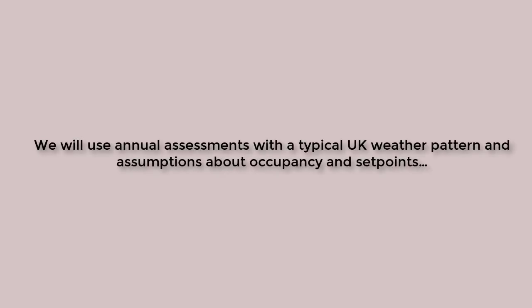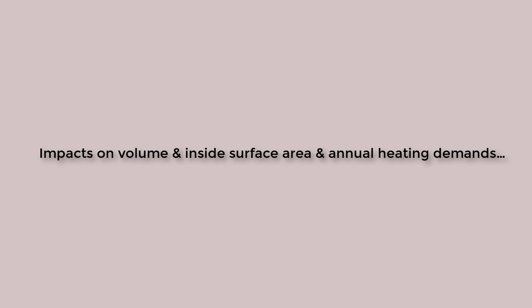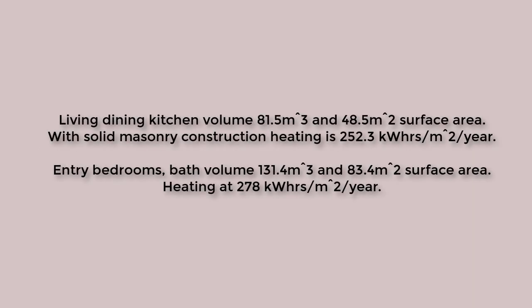For each of the models, I ran an annual simulation using a typical UK weather pattern — in this case Leeds — with a diversity of occupancy and heating set points typical for the living and non-living spaces. What is of interest is what differences the change in reveals introduces in terms of the internal volume of the dwelling and the total internal surface area. With no reveal, we get the initial volume and inside surface area for the living and non-living spaces. Given that the wall is an older-epoch solid masonry wall, it's not surprising that the building performs poorly in terms of kilowatt hours over the year.